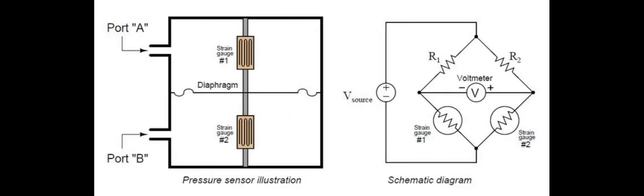There are different types of design in how these differential pressure transmitters work. You do have a strain gauge, for example, which when a force is applied, the strain gauge will deform and the electrical resistance will change. This can also be used in an electrical circuit to give you your 4 to 20 milliamp output, but the capacitance type is one of the most robust and most frequently used in industry today.